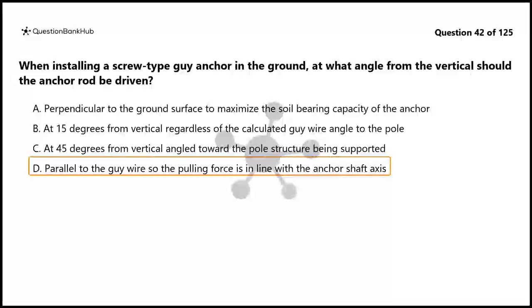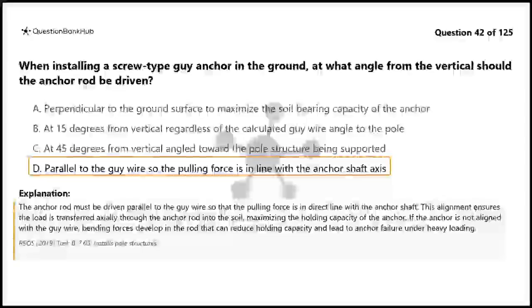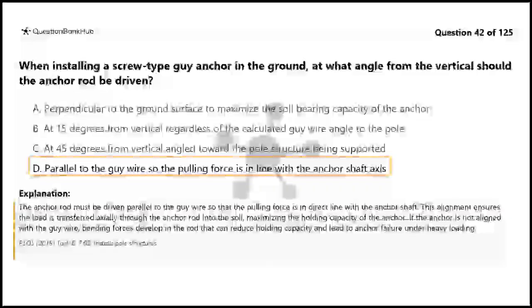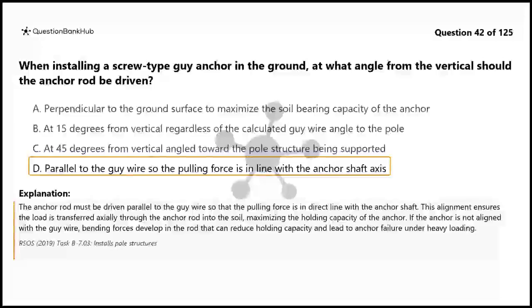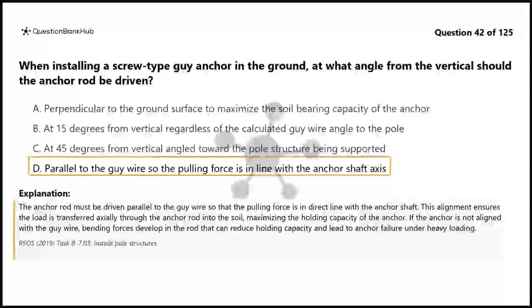The correct answer is D. The anchor rod must be driven parallel to the guy wire so that the pulling force is in direct line with the anchor shaft. This alignment ensures the load is transferred axially through the anchor rod into the soil, maximizing the holding capacity of the anchor. If the anchor is not aligned with the guy wire, bending forces develop in the rod that can reduce holding capacity and lead to anchor failure under heavy loading.